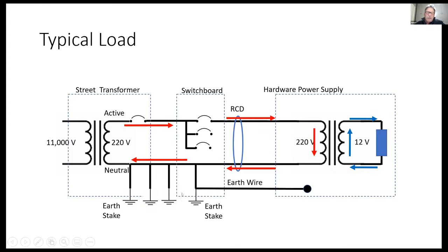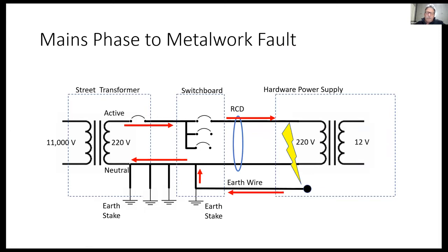So on the left-hand side, you can see the mains is earthed. One side of the mains system is earthed. In my diagram here, the secondary is not. And it's quite happy. There's absolutely nothing wrong with that. So now what we do is say, okay, let's have a look at some fault conditions. So here's an active shorted out to the metalwork, and you can see now where the current flows. It's still down the active, down through the short circuit to the metalwork and back along the earth wire. And in this condition, the RCD is unbalanced, and so it would be trying to cause a trip.